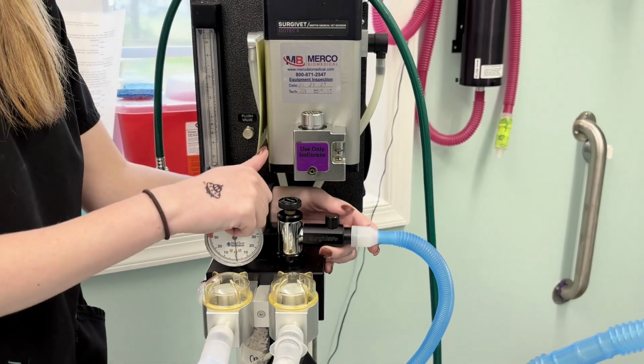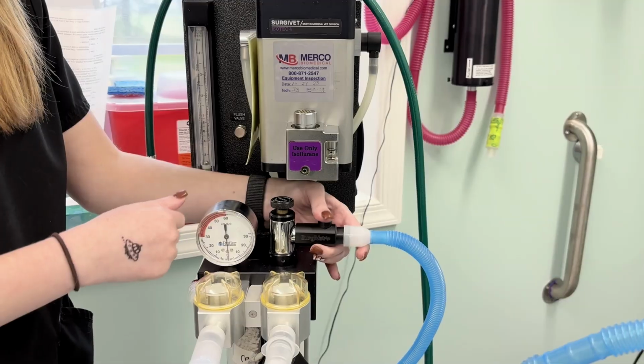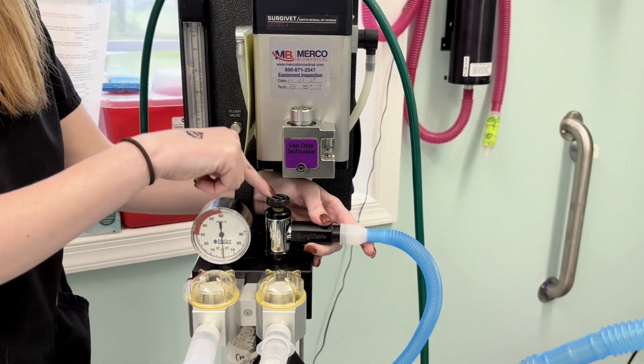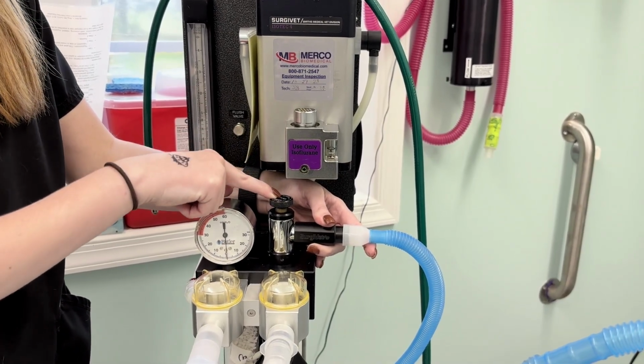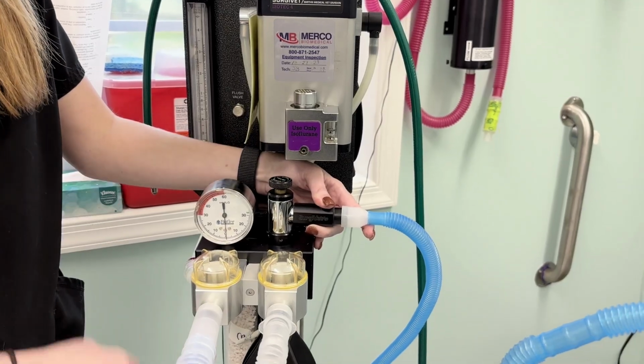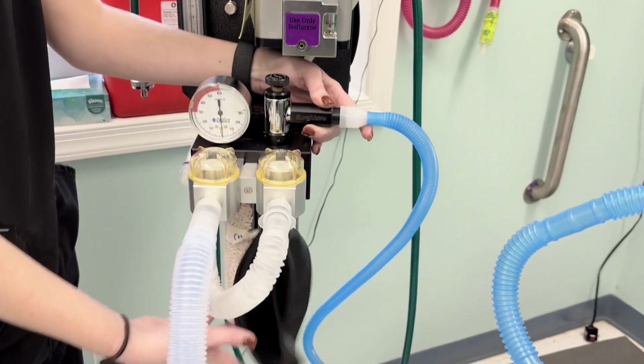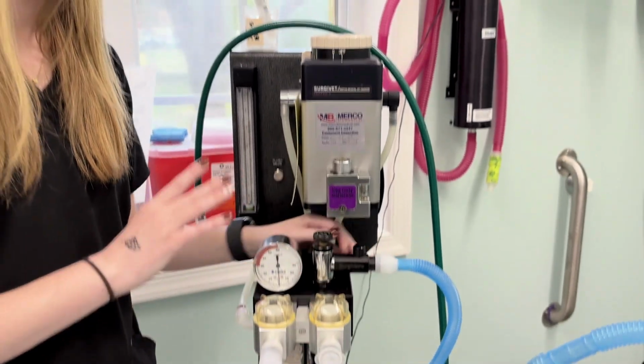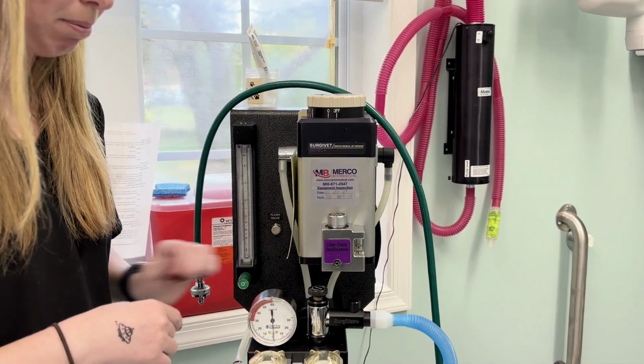Right here is the quick release for the pop-off valve. Instead of turning off the pop-off valve, you can press this down, and that'll basically do the same thing. Then you can give a breath that way, and once you're done, you just let up and it's back open, so you don't have to remember to turn this back open.